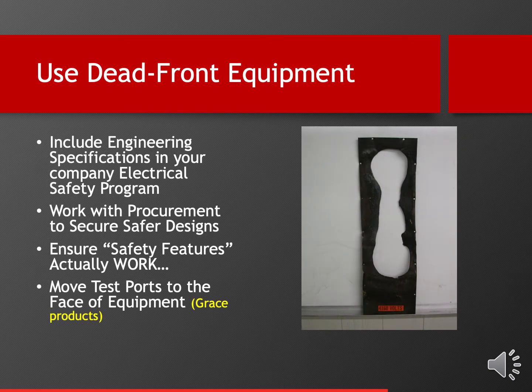The use of dead front equipment. Well, what you see on the right side of the picture on the right is what used to be a dead front panel cover. It's a 4160 volt system, but don't confuse this. This can absolutely happen at low voltage as well. But here you see that an arc developed behind that door that lasted longer than 2 seconds, and it melted a hole in steel. And there was enough residual energy that came through that hole that was made by the arc to actually injure or kill the person who was standing near that.